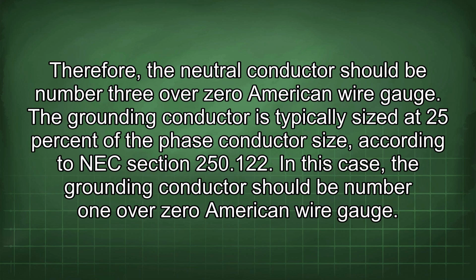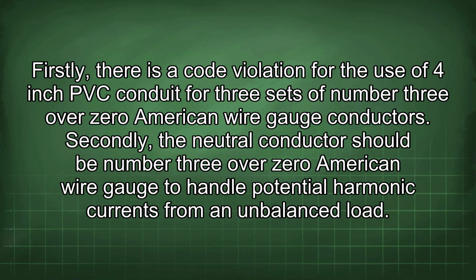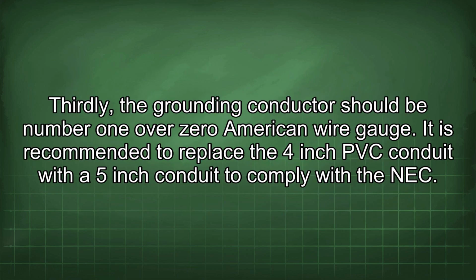The grounding conductor is typically sized at 25% of the phase conductor size according to NEC section 250.122. In this case, the grounding conductor should be number 1/0 American wire gauge. Firstly, there is a code violation for the use of 4-inch PVC conduit for 3 sets of number 3/0 American wire gauge conductors. Secondly, the neutral conductor should be number 3/0 American wire gauge to handle potential harmonic currents from an unbalanced load. Thirdly, the grounding conductor should be number 1/0 American wire gauge.